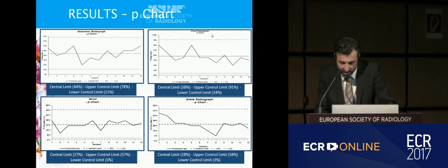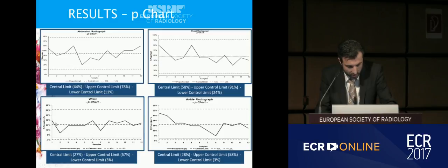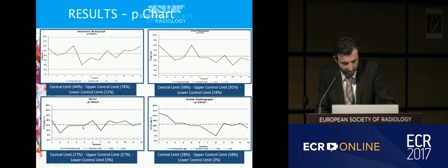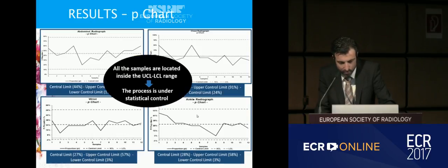In the chest radiograph, we have also the P chart, and we can see the central line is around 58%. For the wrist, we have a central limit of 27%, and in the ankle radiograph, we have a central limit of 28%. All the samples are inside the limits.